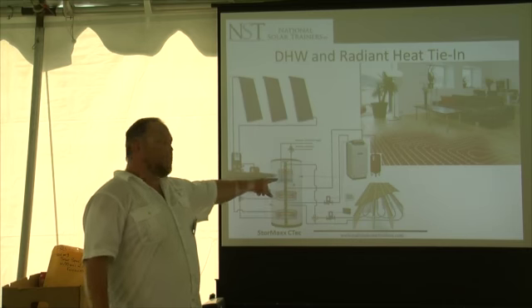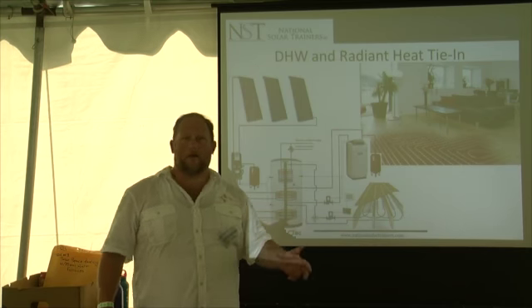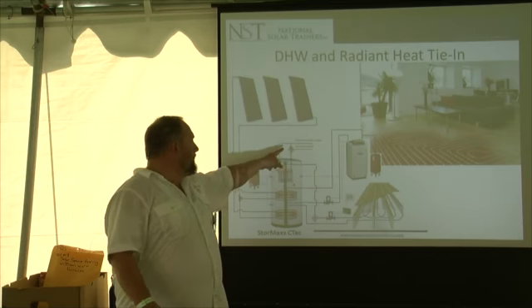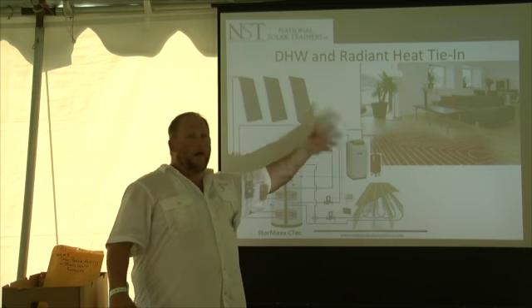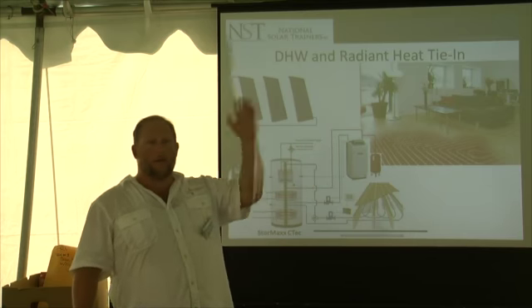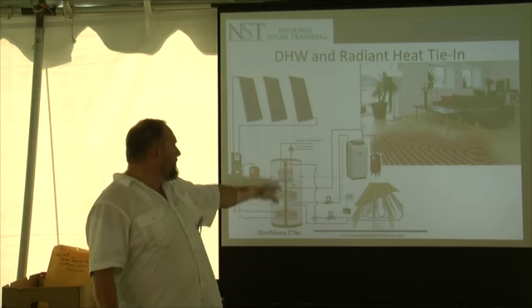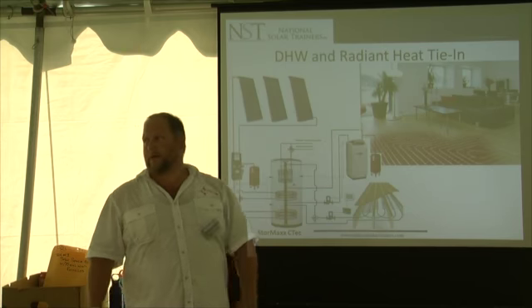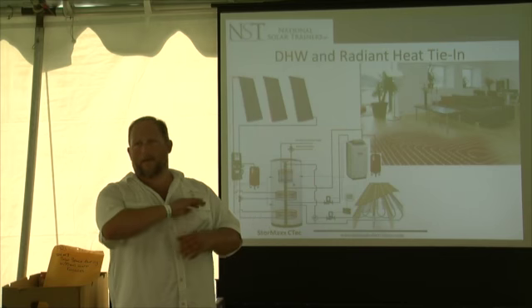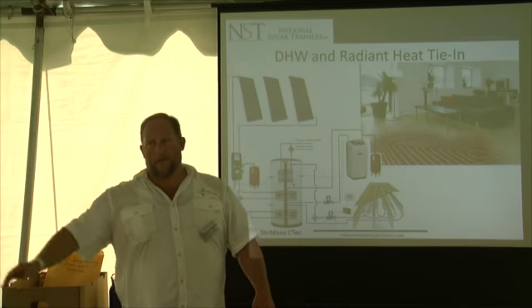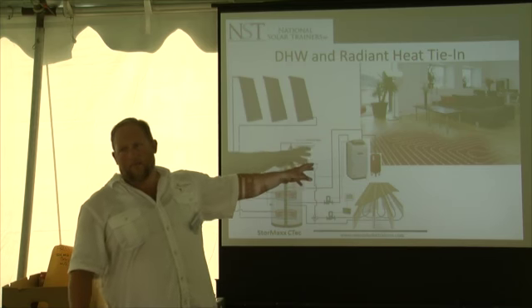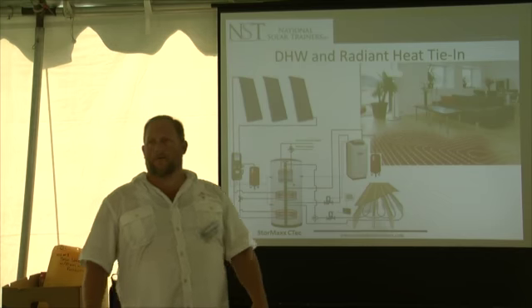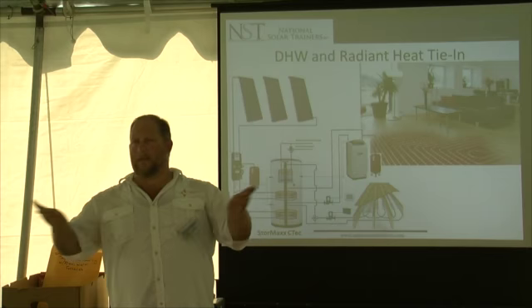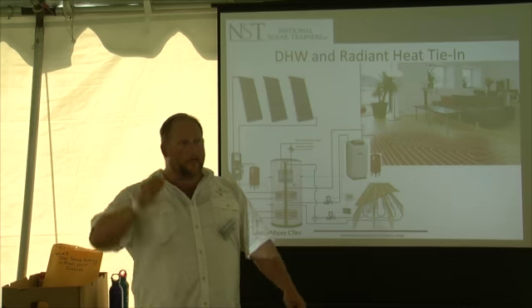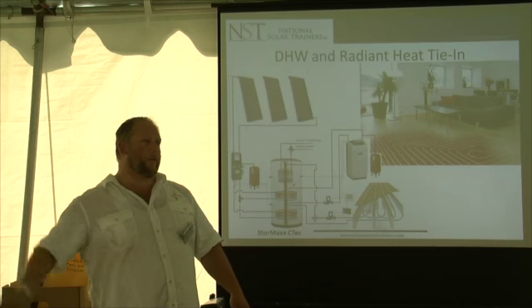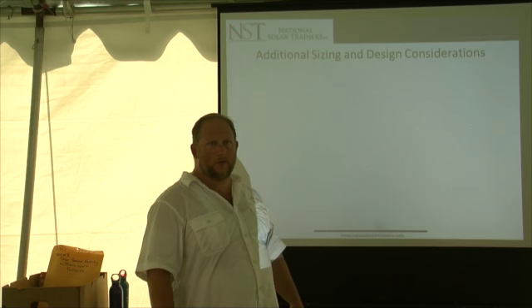So you have multiple coils. The top coil is sort of an on-demand. This is a solar on-demand hot water tank for domestic. Cold water comes in on the top at well temperature, comes out of this coil up to 105 or 110, and right to the shower heads. And then the volume of water in the tank is what's circulated into the floor at 15 psi. So you're circulating the entire volume of tank water through the floor loops, and you're separating the domestic through this coil on the top, right? And you have no issues with infection, Legionella, anything like that. They're separate. You have a 200, 300 gallon storage tank, and that entire volume is what's being circulated through the floor. This is one of the newest ways to do it.